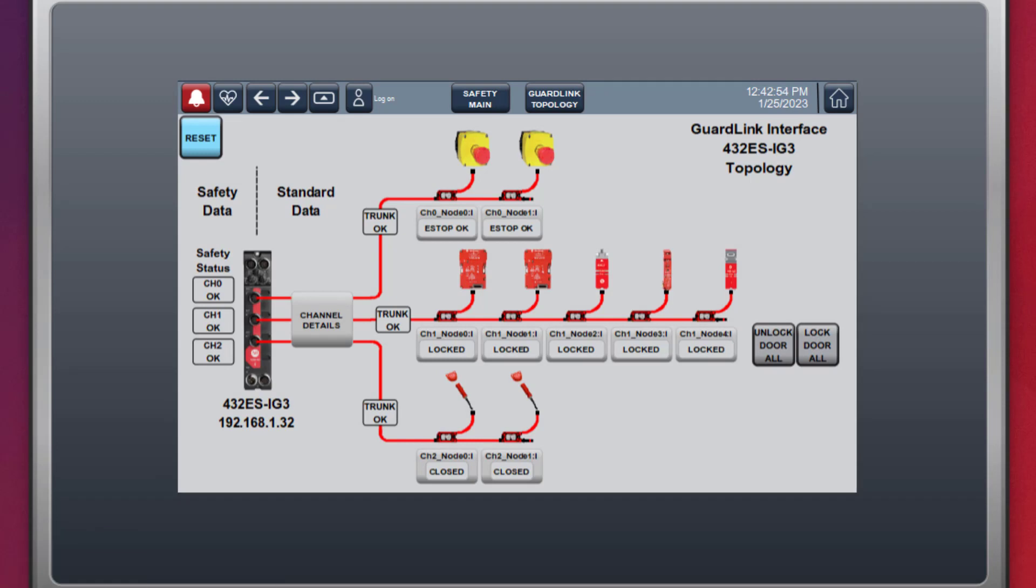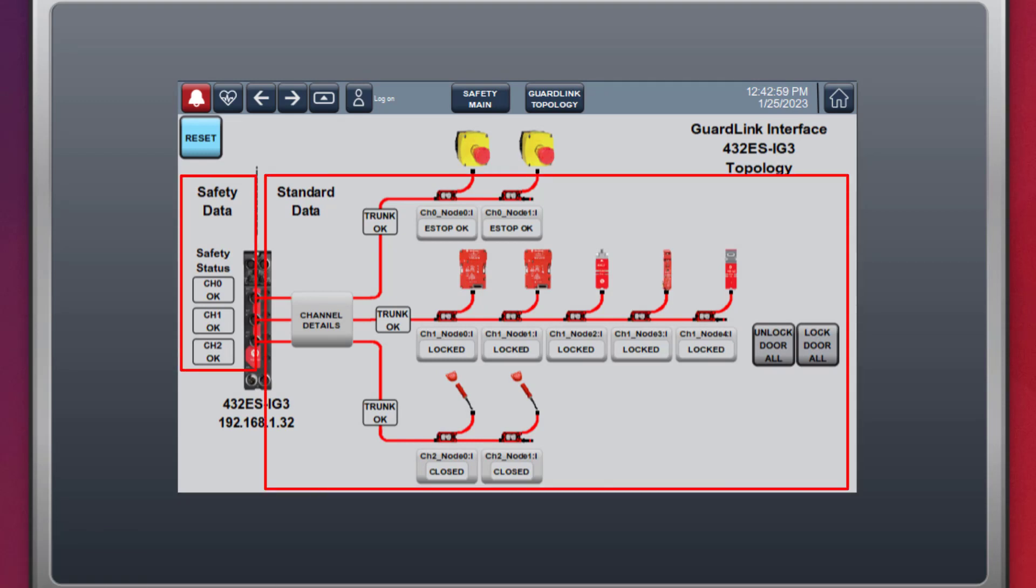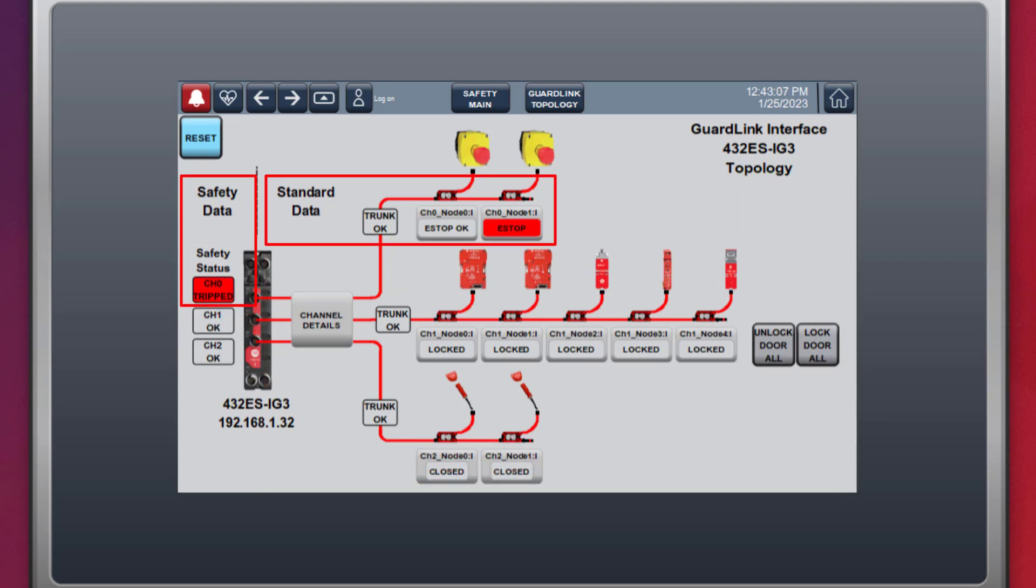The topology view shows the safety status and standard node feedback for each device. When an e-stop is pressed, the safety-rated channel 0 status is tripped, and the standard data indicates which e-stop has been tripped. The node faceplate can be used to get detailed information from the GuardLink node.